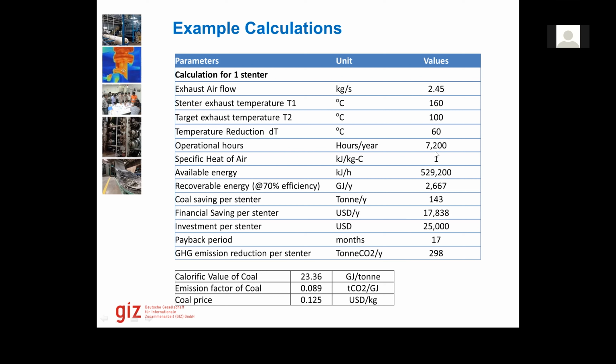Operation hours were 7,200 hours a year. And the specific heat was for this air, because this was running on thermal oil. So we don't have a flue gas in this case. We have just hot air, and specific heat is usually 1 in this case. If we have a burner installed that is for natural gas, then we need to use specific heat of flue gases rather than specific heat of common air. So just remember that you need to change this value in that case. Then available energy was calculated using Q = m Cp delta T. Cp is 1, delta T is 60, and m is 2.45 kilogram per second.